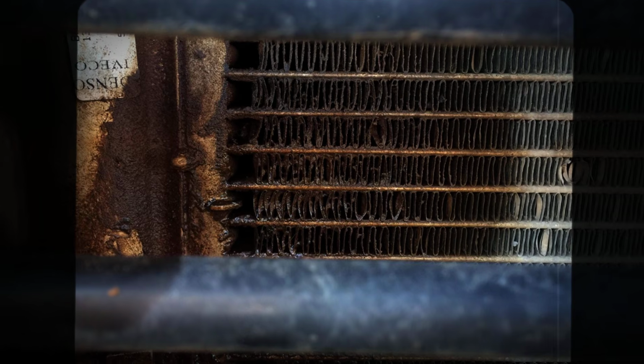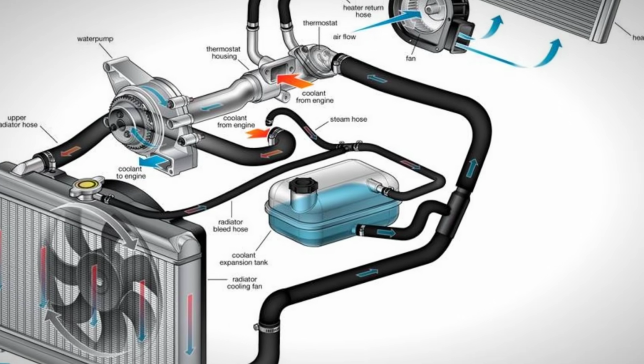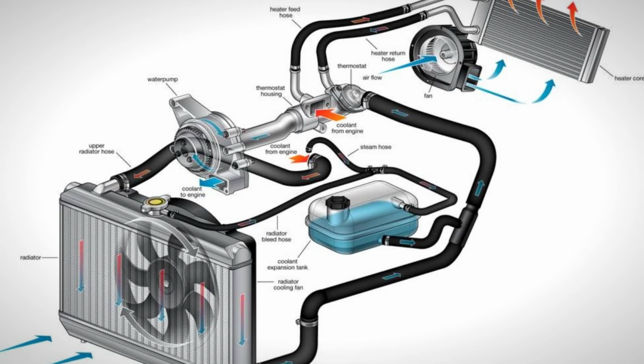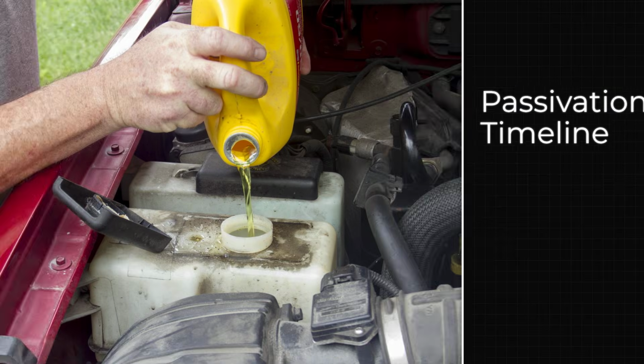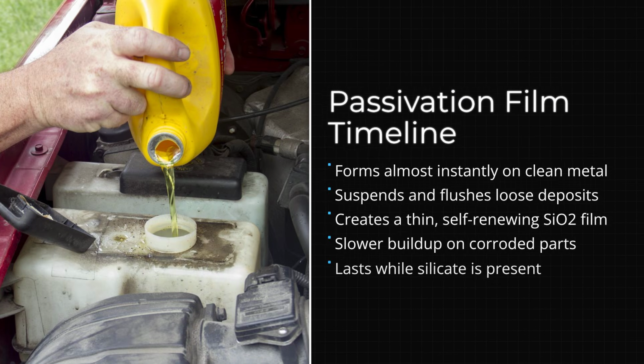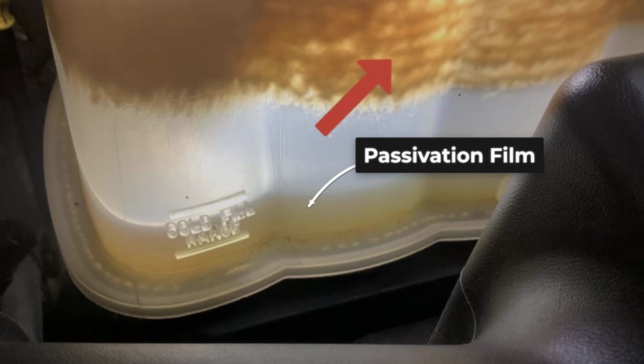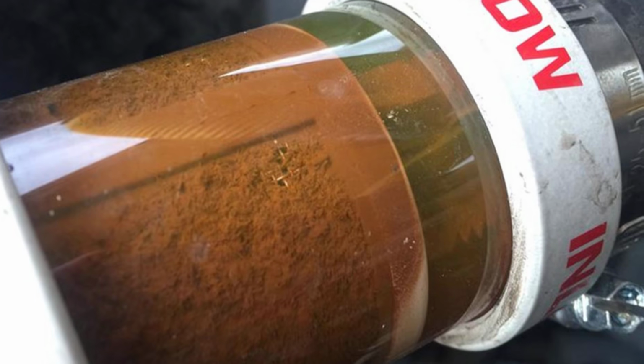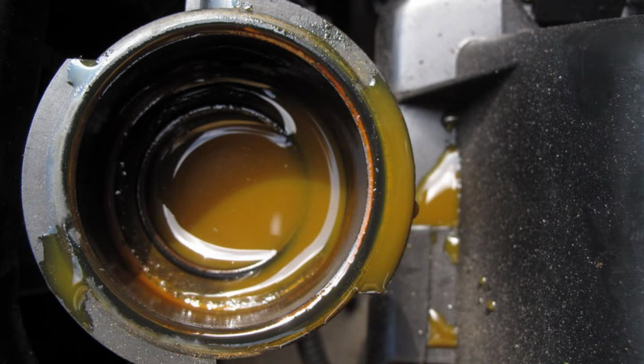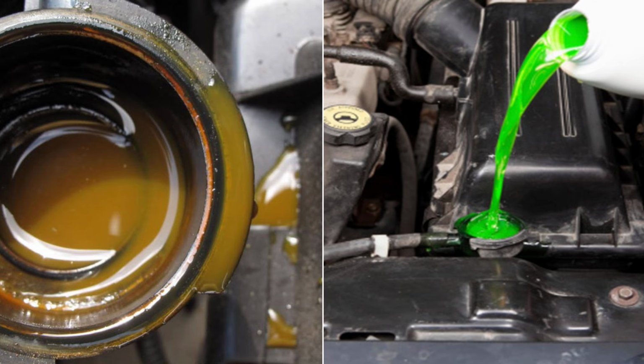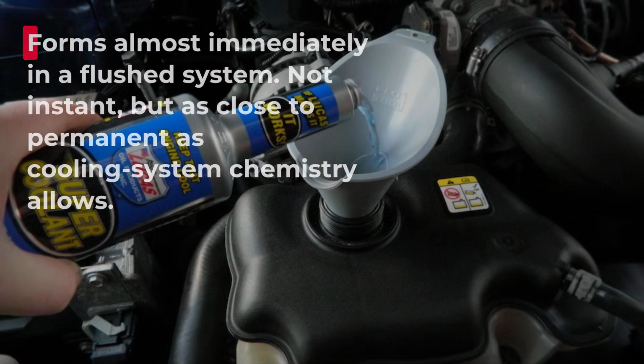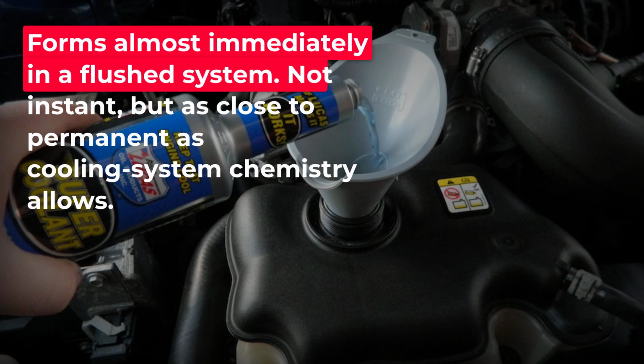In an older system with some light surface oxidation or loose deposits already present, the compound does two things simultaneously: it suspends and carries away the loose material while laying down the passivation layer on the clean surface underneath. You'll sometimes see a faint brownish tinge develop in the coolant reservoir over the first week. That's the suspended material being carried out of the circuit and collected, and then the coolant gradually clears as the system stabilizes. Not instant, but as close to permanent as cooling system chemistry allows.